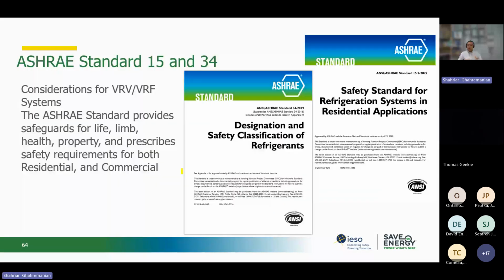There are many standards if we consider VRF systems actually. There are many standards like ASHRAE standard 15 and 34. ASHRAE standard 34 is for safety of the refrigerant, and ASHRAE 15 is about the safety standard for refrigerant systems. If we have a residential system where we need to install the VRF, it's better that we also review these ones for our facilities and make sure that we comply with these ASHRAE standards.